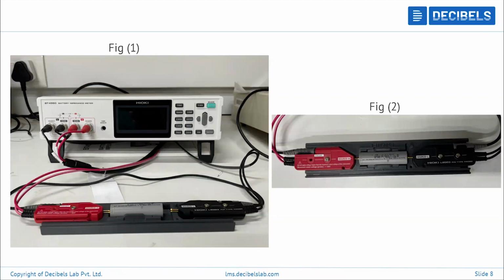So yeah, that is the difference. So here, this is the machine, and with this you can conduct EIS and even the impedance test at particular frequencies, and an EIS sweep. This has some limits in terms of frequency range. We will see them in the next part.